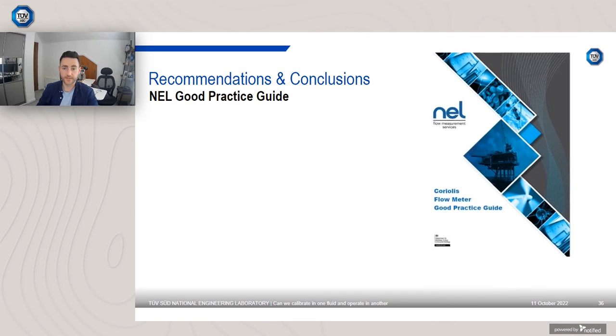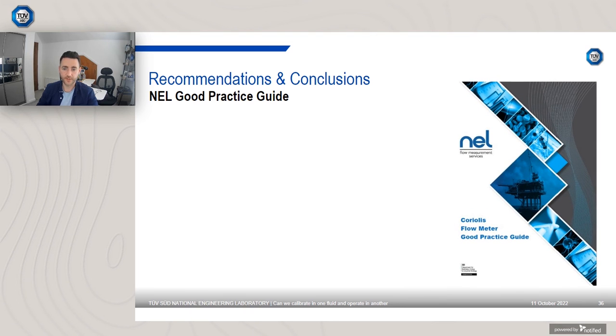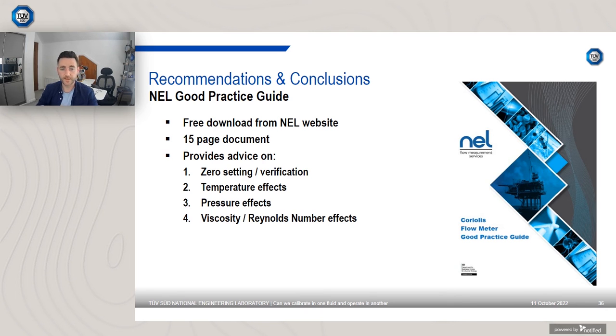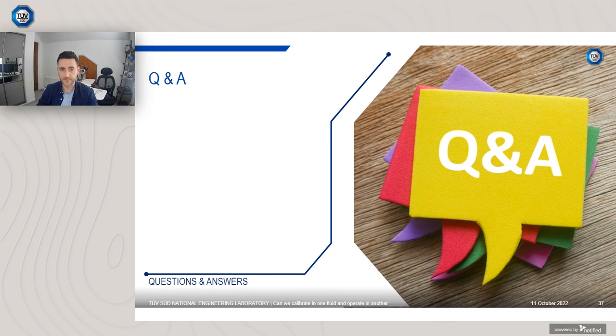So I mentioned that good practice guide. This is the front cover here. I recommend if you're interested in Coriolis meters, you may want to download it. It's free from the website, so if you want, search for Coriolis Flow Meter Good Practice Guide, NEL, or TÜV-SÜD, NEL. It's a 15-page document, and it provides advice on zero setting, verification, temperature effects, pressure effects, and also viscosity and Reynolds number effects. So all the components that we're aware of that differ between a calibration facility and service conditions.